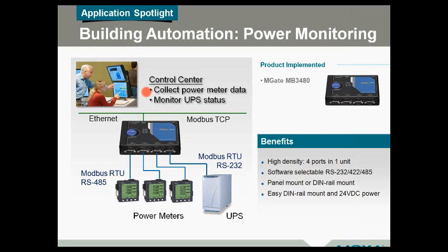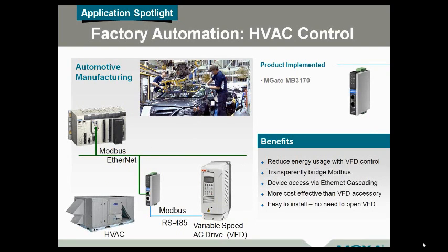And if this is merged within your group in a facility, whether it be a control room or even a data center application where there's critical power needs, a lot of the larger commercial UPS systems also have options, whether built in or an option card, to monitor an uninterruptible power supply via Modbus. So great application on how you can instrument the existing systems and bring that into your control center to measure your energy usage and be more efficient at how you use that and find out what you can do to conserve energy.